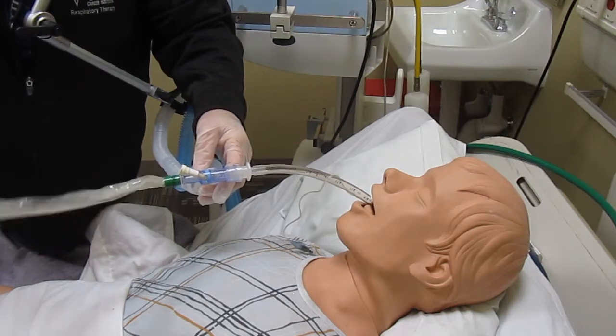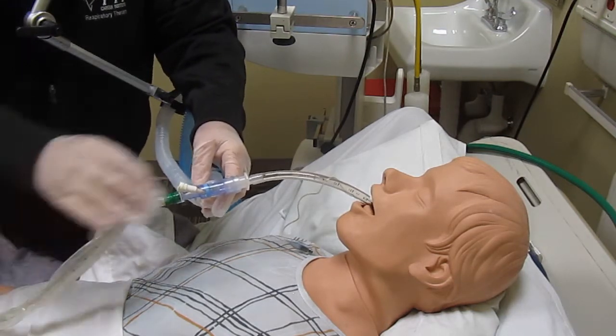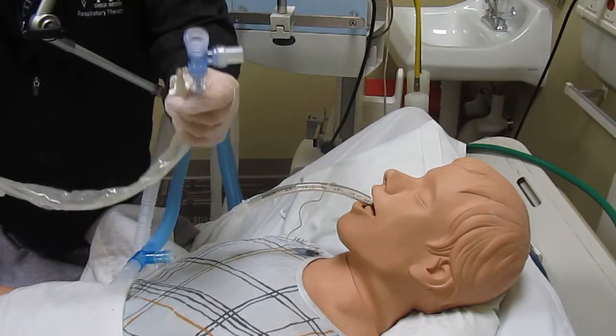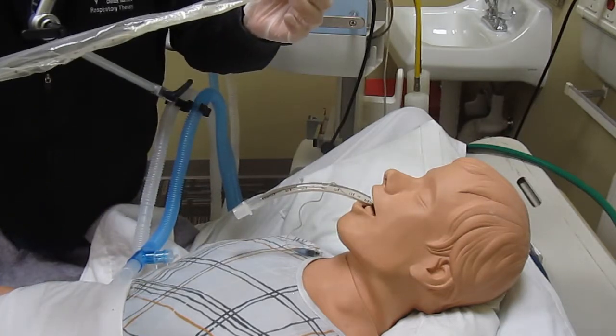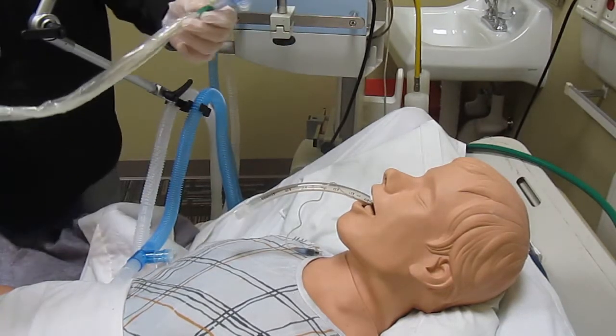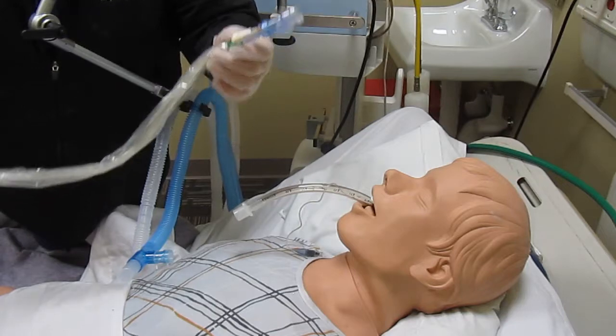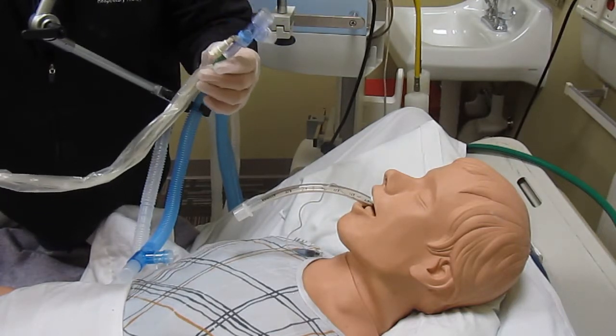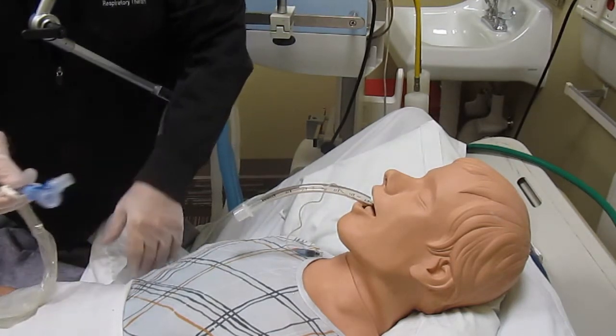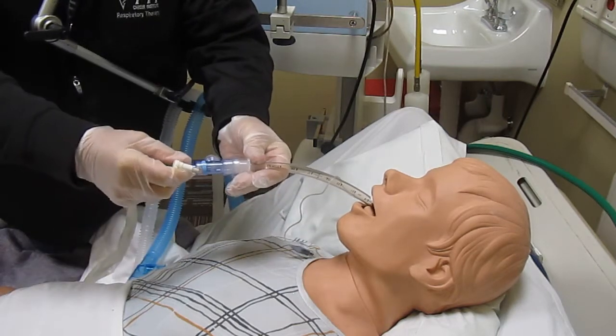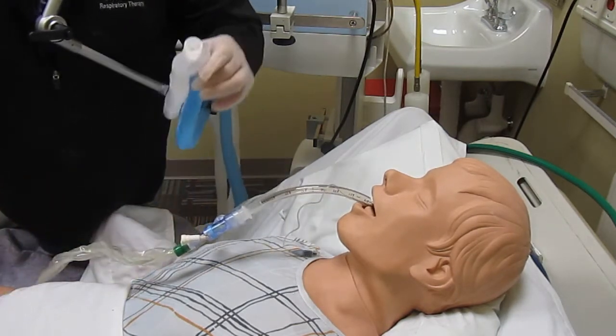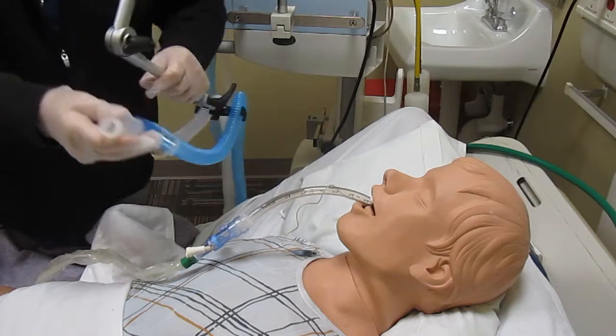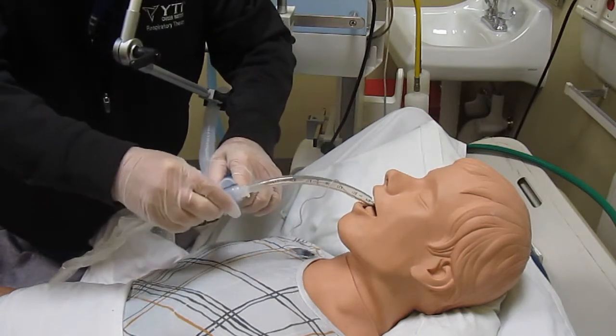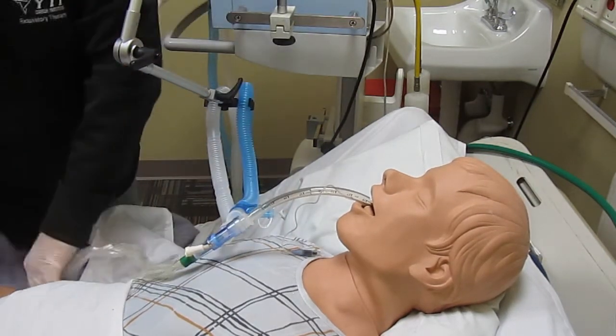This setup is an inline suction setup. As you can see, it is an elbow with a suction catheter encased in plastic so it's not contaminated, and is used over and over again on the same patient. It connects to the endotracheal tube. The elbow from the ventilator circuit is removed, and this connects to the ventilator circuit.